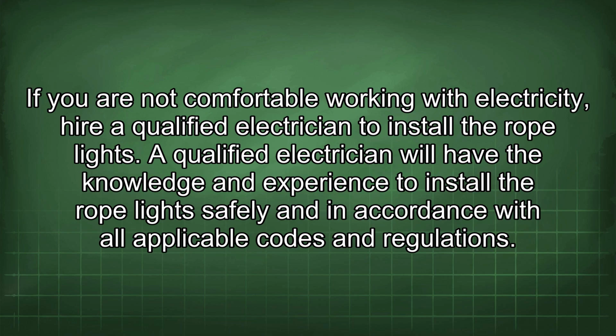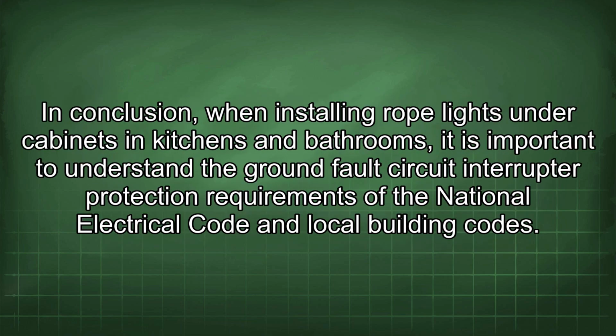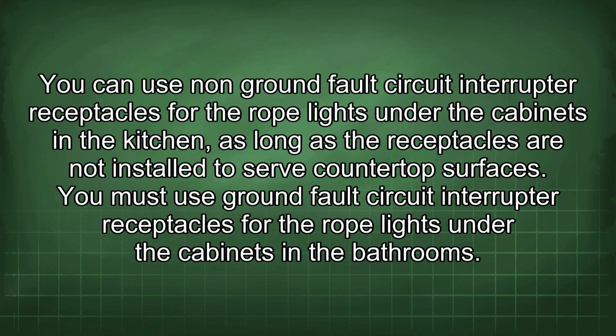In conclusion, when installing rope lights under cabinets in kitchens and bathrooms, it is important to understand the ground fault circuit interrupter protection requirements of the National Electrical Code and local building codes. You can use non-ground fault circuit interrupter receptacles for the rope lights under the cabinets in the kitchen, as long as the receptacles are not installed to serve countertop surfaces. You must use ground fault circuit interrupter receptacles for the rope lights under the cabinets in the bathrooms.